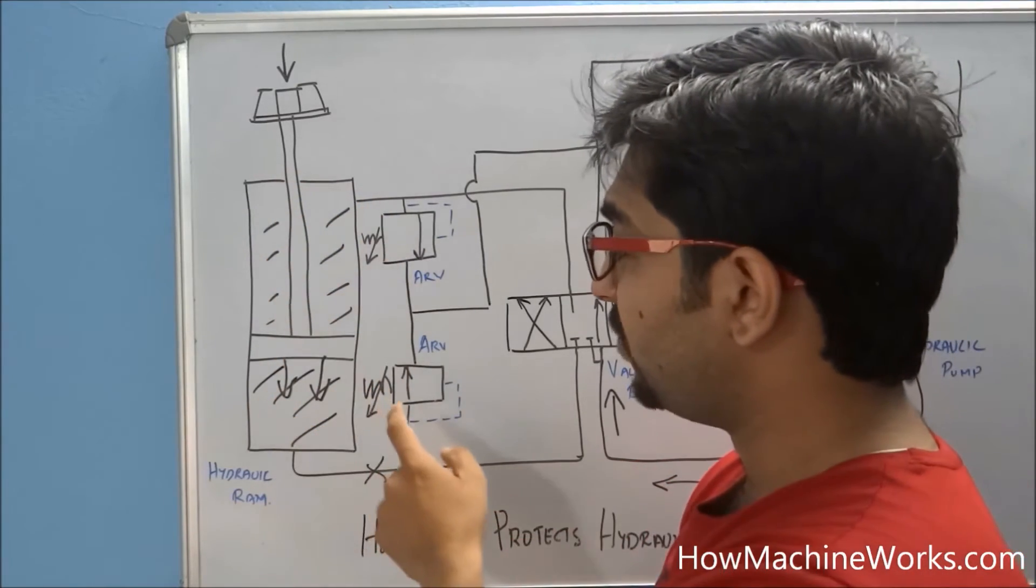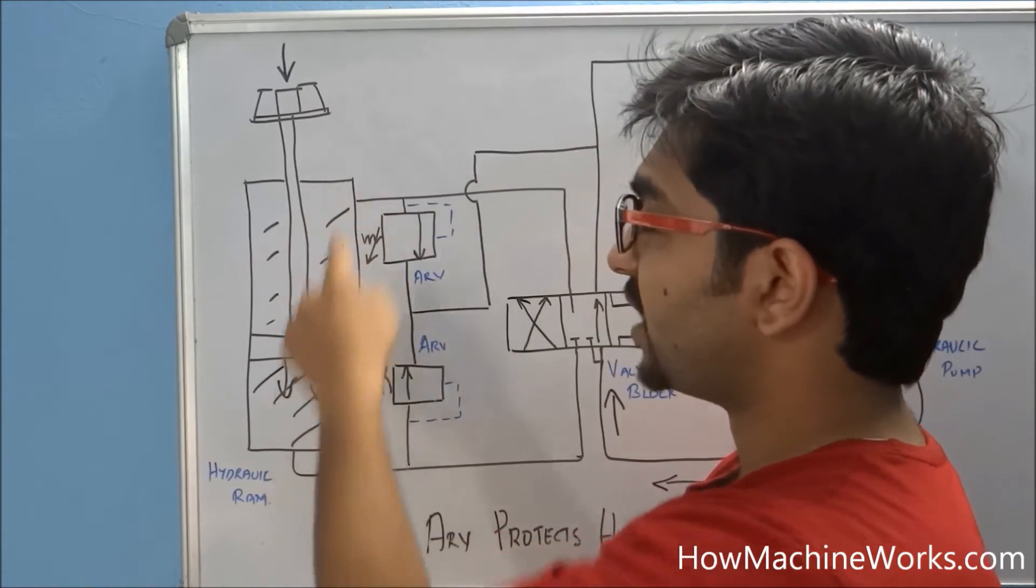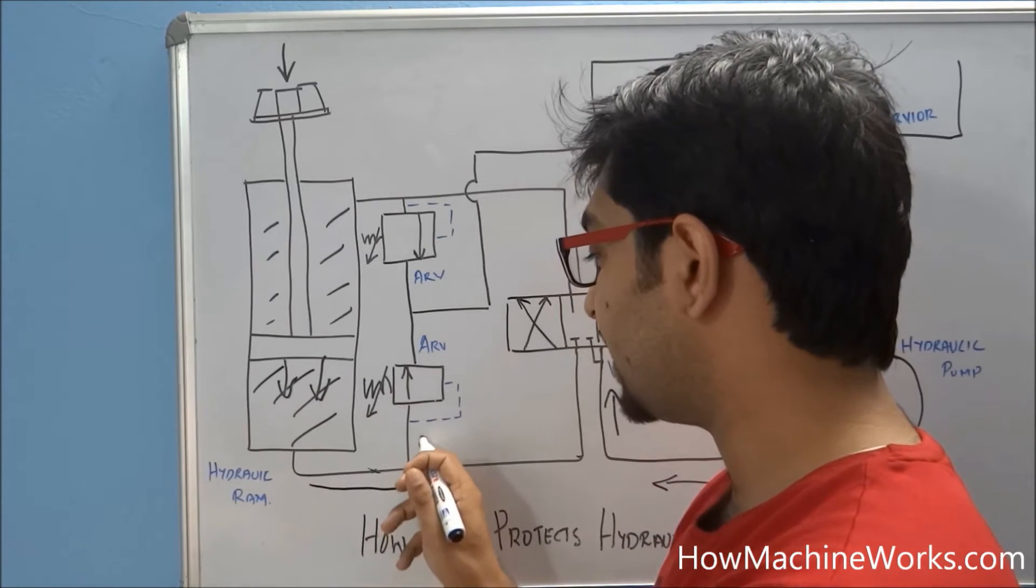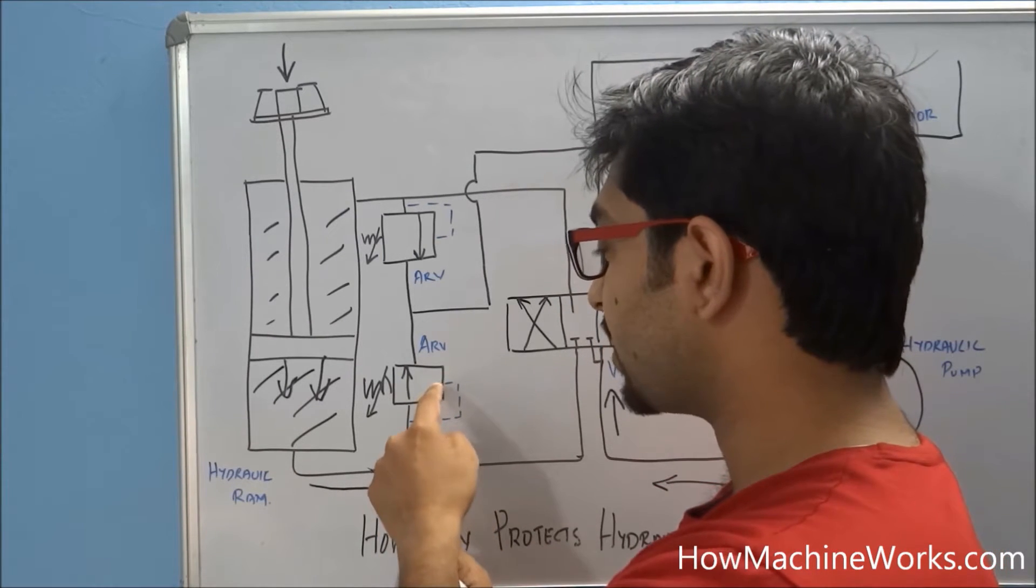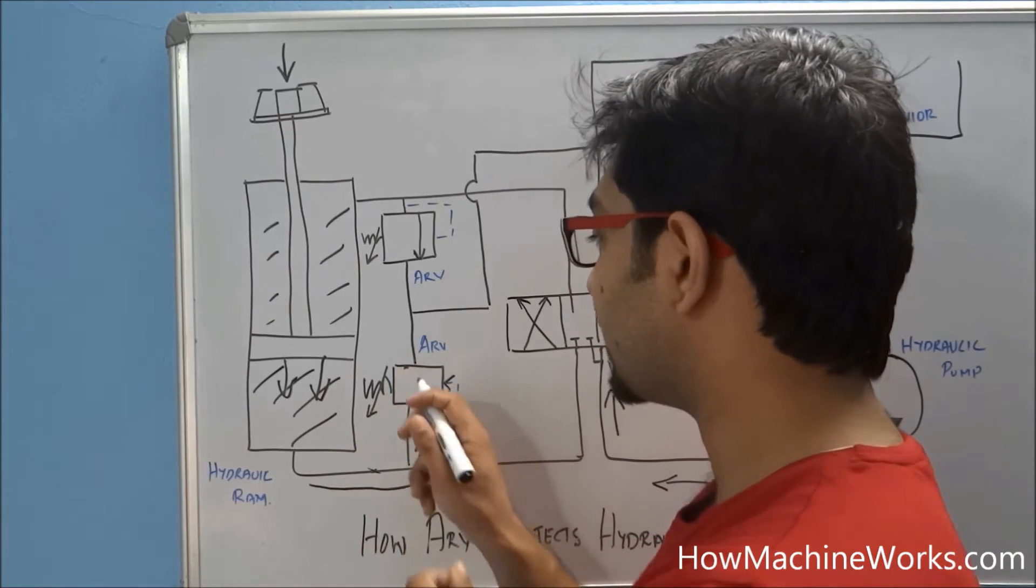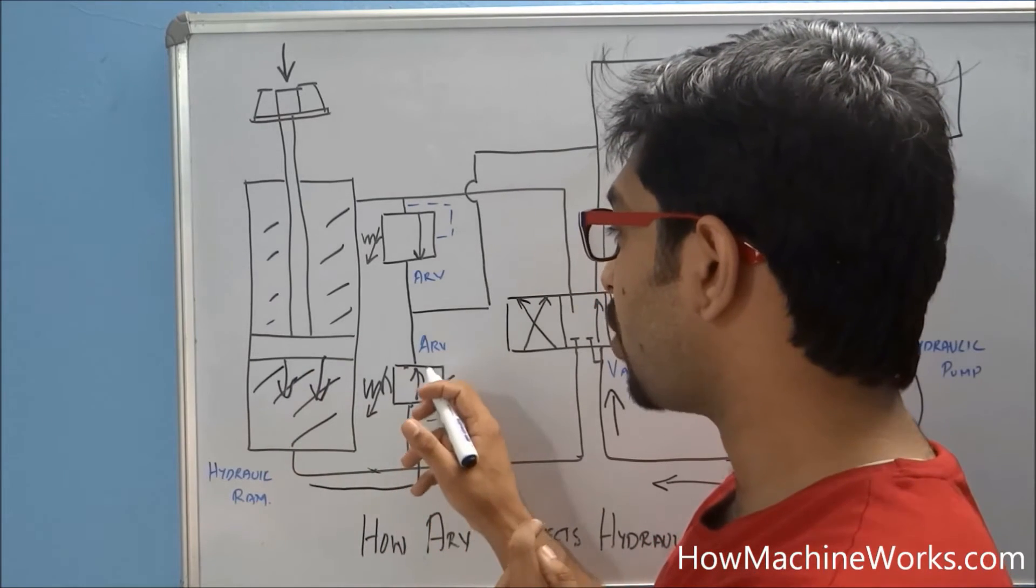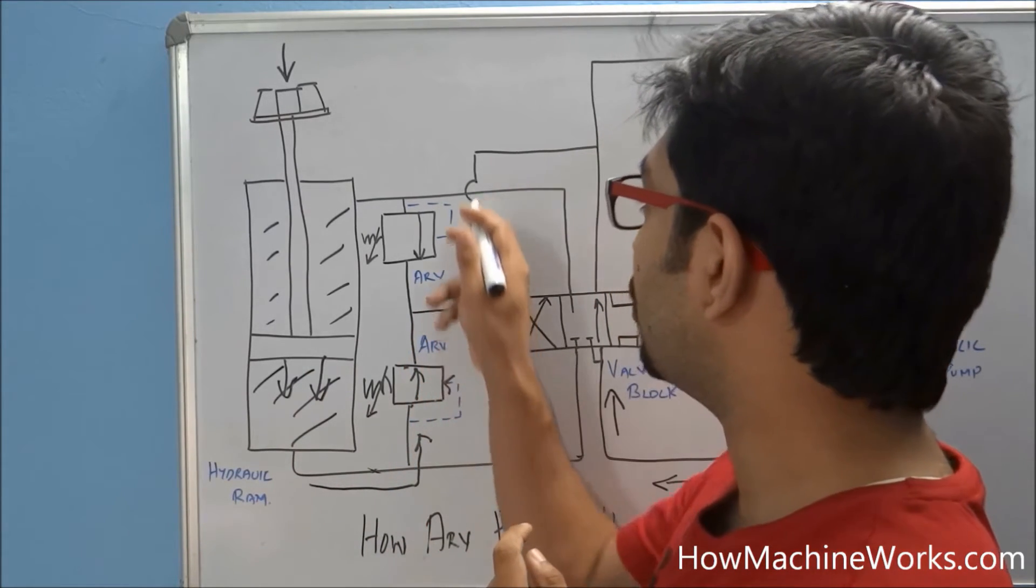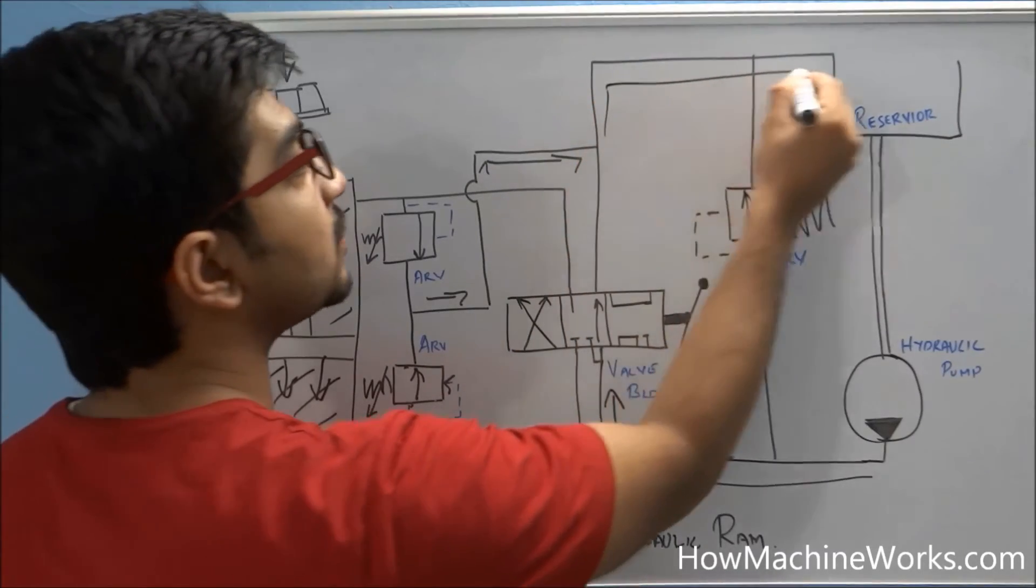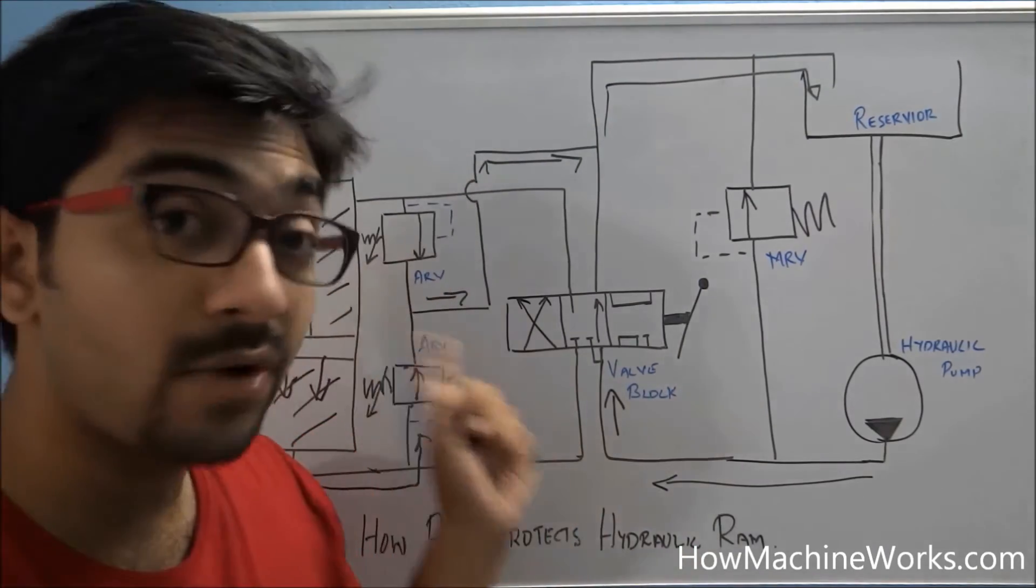To avoid such failures and protect the hydraulic ram, we have auxiliary relief valves both in the head side and rod side of the hydraulic ram. When excess pressure is coming, it hits the auxiliary relief valve and the auxiliary relief valve moves - you can see this arrow gets aligned. The excess pressure will be vented through the auxiliary relief valve in this direction and goes towards the return line, back towards the hydraulic tank, thereby protecting the hydraulic ram.